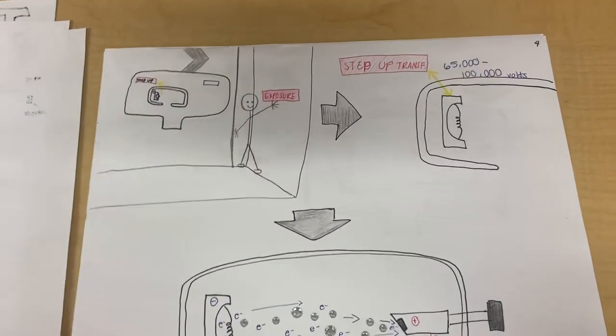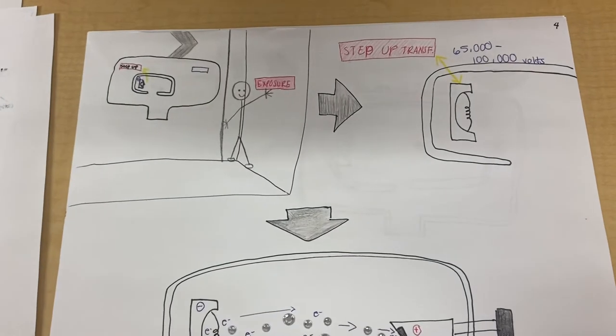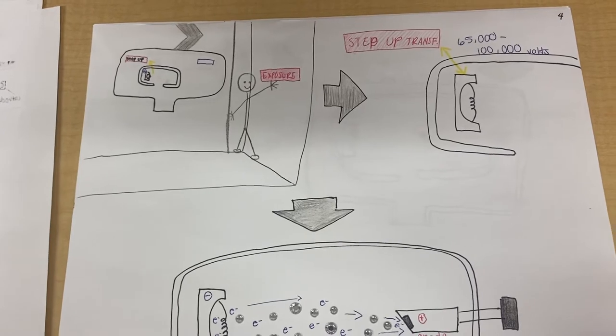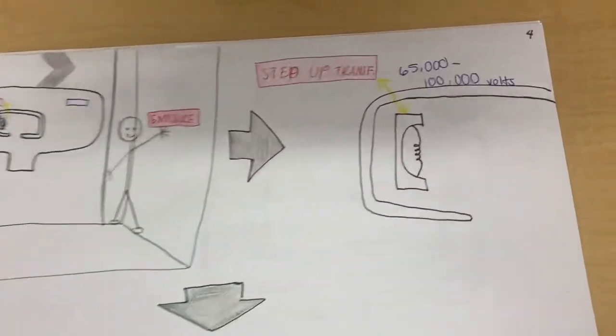So then going on, the clinician, hidden by a nice lead-lined wall, will press the exposure button. The line current will then enter the step-up transformer, also known as the high-voltage circuit, see here.